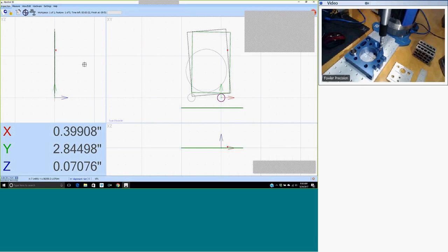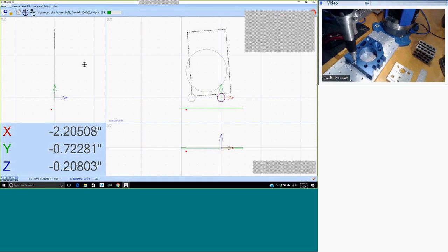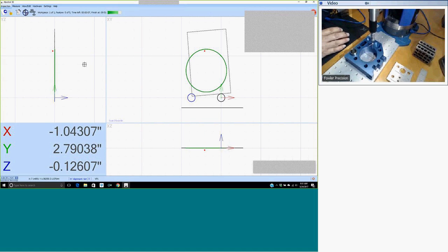With direct computer control, I can use this program to measure a part perfectly, vectoring to the surface, vectoring at the same speed every time, which I could never do by hand. I could never measure perpendicular to the surface every time manually. So this is where the repeatability and a lot of the accuracy comes in with the zCAT.